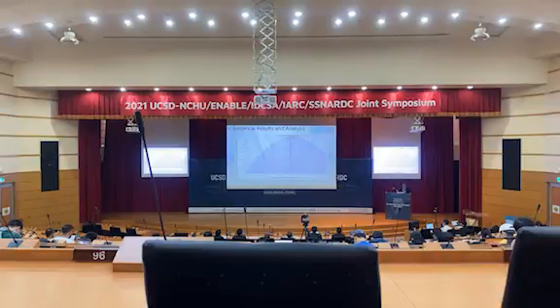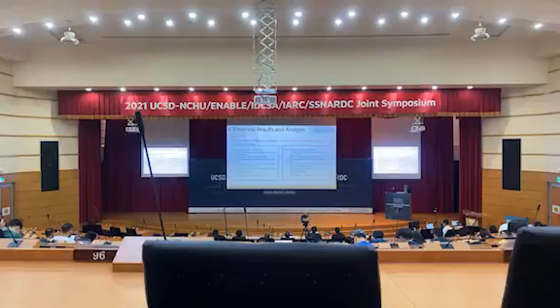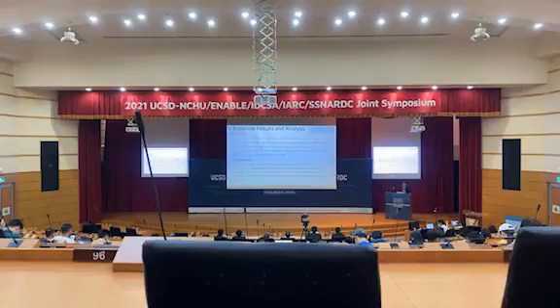And this figure shows from 76 to 150, the 119 here as the highest total amount of electricity bill saved. That's on the vertical. You can see that picture. So, as a result, scenario 1 shows, in the red box here, that we can have a positive net present value of over 2.3 million NTD. So that's for scenario 1. We just changed the capacity contracted with Taipower.